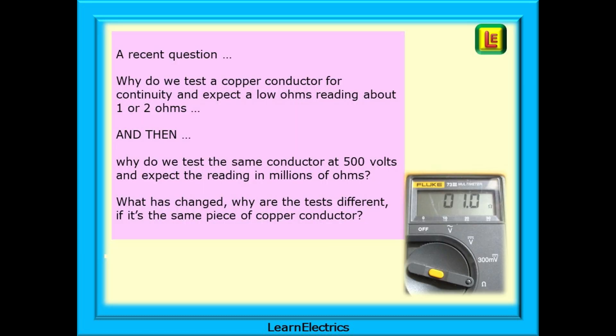The question that was asked was: why do we test a copper conductor for continuity and expect a low ohms reading of about one or two ohms, and then why do we test the same conductor at 500 volts and expect the reading in millions of ohms? What has changed? Why are the tests different if this is still the same piece of copper conductor?